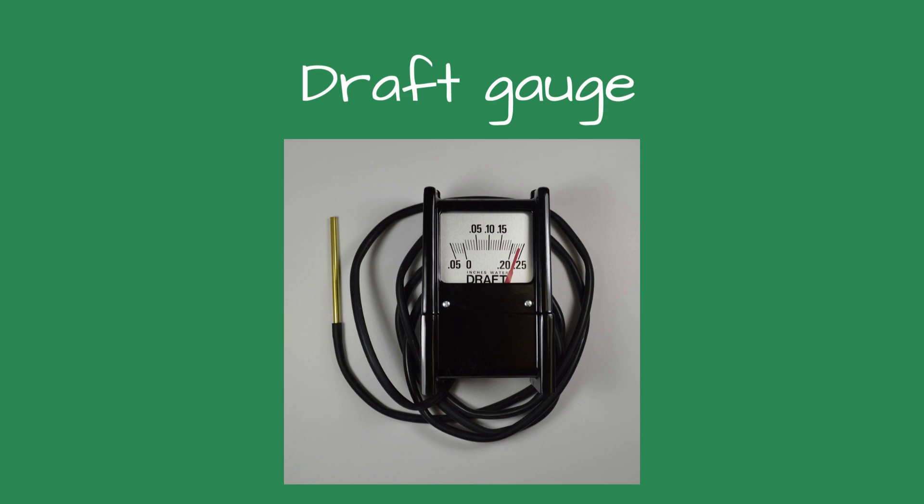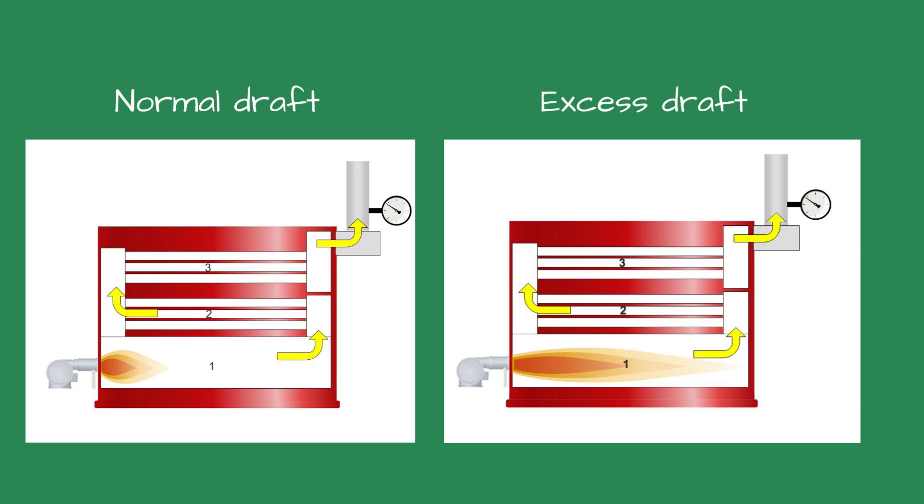On cold days, the draft may be very high. The excess draft could pull the flue gases too quickly through the boiler. This wastes money as the heat does not have time to transfer to the boiler. Instead, it is wasted up the stack. In some instances, the high draft could pull the flame off the burner resulting in flame failures.